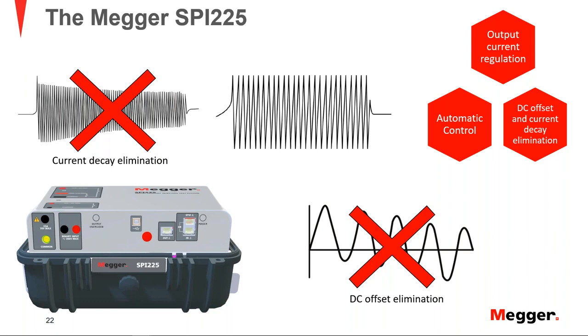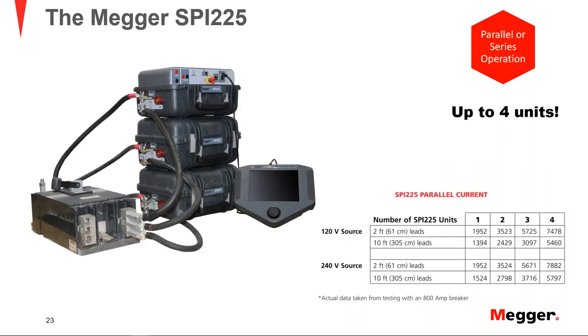In terms of the output, whenever you need higher than 2000 amps, the SPI can use more units either in series to increase the voltage in the output or in parallel to increase the current capability. The system can daisy chain up to 4 units together. I'm showing you here a table as an example, with data taken using an 800 amp breaker. You can see that with 4 units, using a 120 volt source, you can achieve close to 7,500 amps. If you're using a 240 volt source, you can achieve close to 7,900 amps.